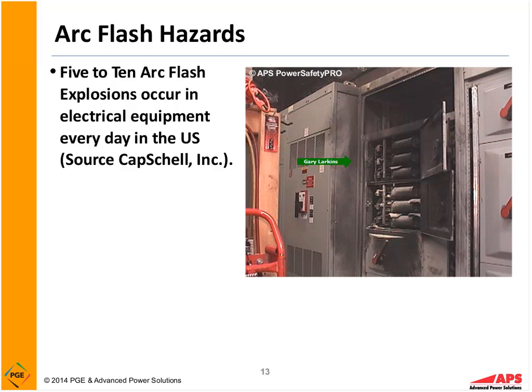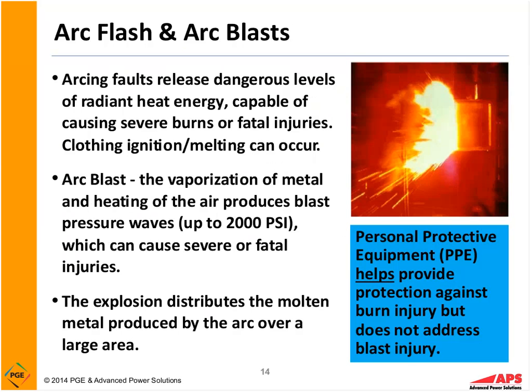So it's very important that when we look at our safety programs and policies, we have a job hazard risk analysis in place. In other words, we're thinking about the hazards, we're paying attention to the potential hazards, and we're providing the appropriate steps to avoid or eliminate those hazards or to protect ourselves against those hazards. So when we look at arc flash and blast, arcing faults release dangerous levels of radiant heat energy capable of causing severe burns or fatal injuries. We also have the blast pressure wave, and that pressure wave can be up to 2,000 pounds per square inch.